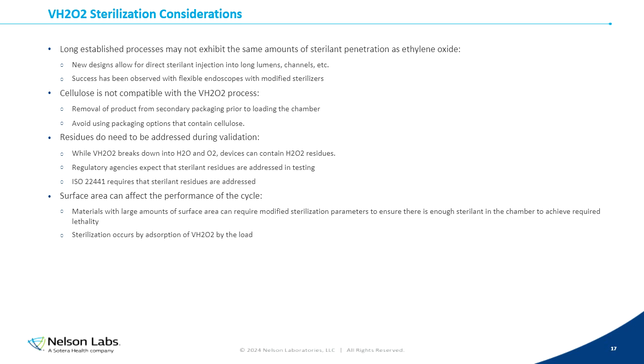I will say though that new process designs, sterilizer designs, et cetera, are allowing for direct sterilant injection into long lumens and channels. And therefore success has been observed with flexible endoscopes with modified sterilizers. So I think gains are being made here and that's something that folks should be aware of. As mentioned, cellulose is not compatible with this process. That requires oftentimes during sterilization that we remove product from secondary packaging prior to loading it in the chamber. And we need to make sure that we avoid packaging options that contain cellulose.